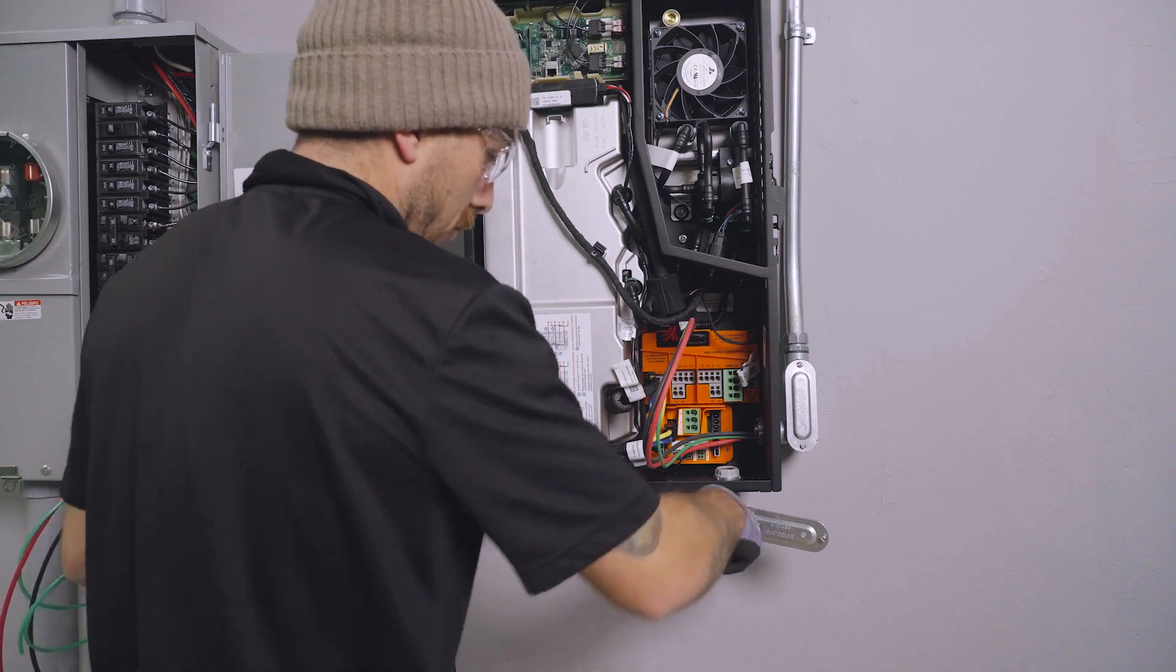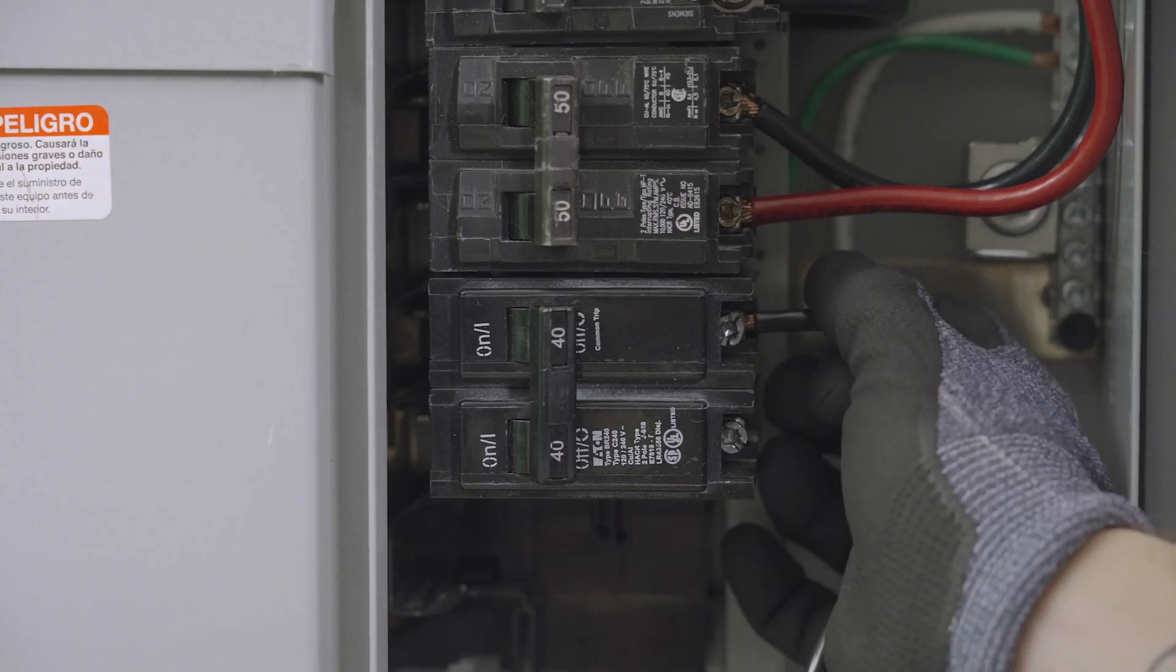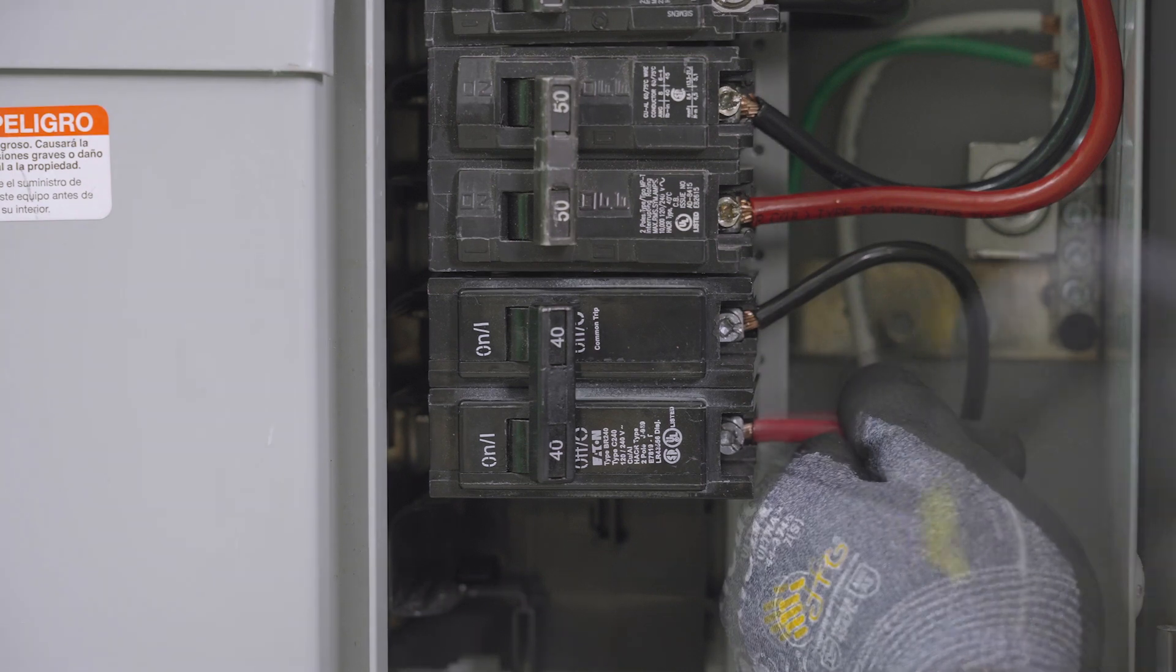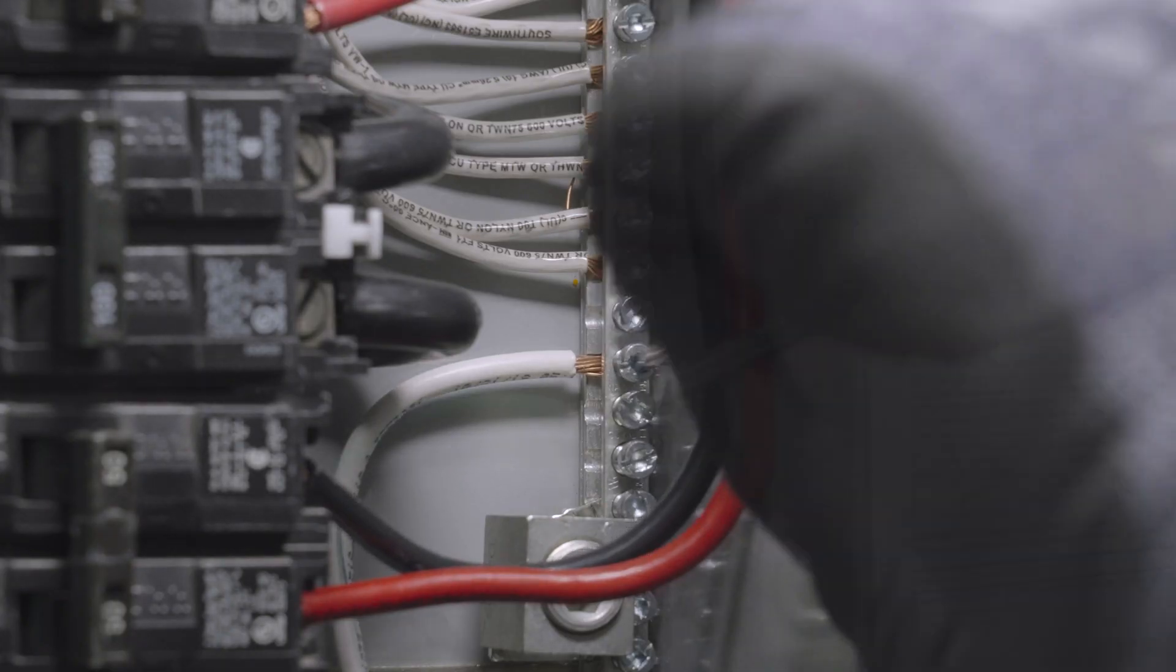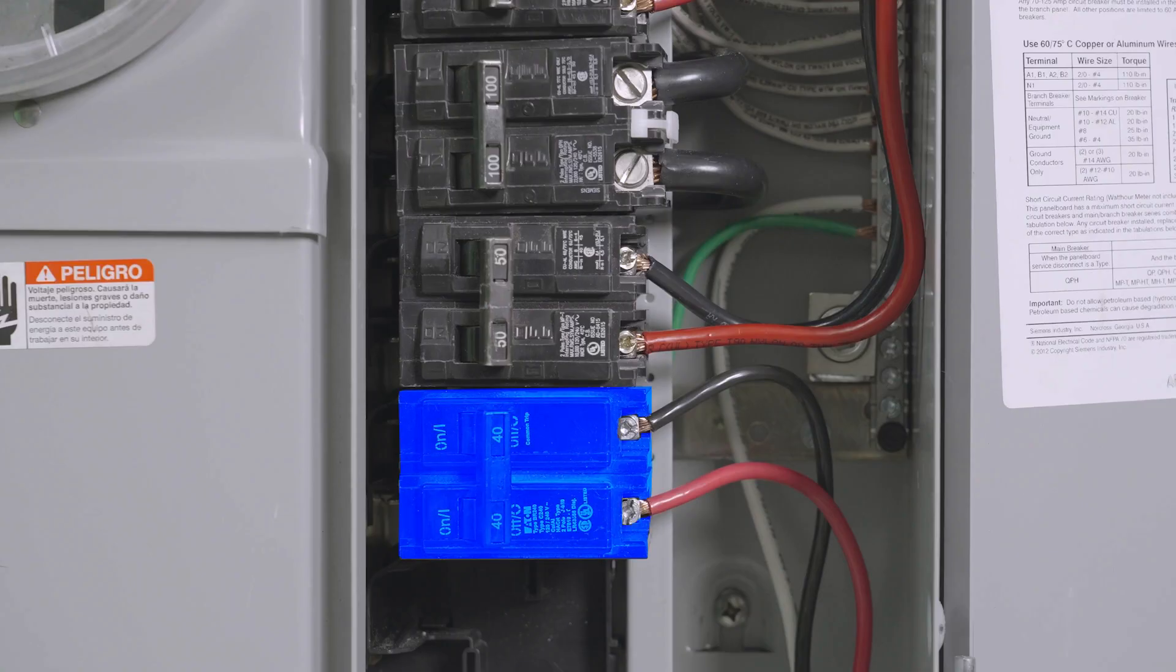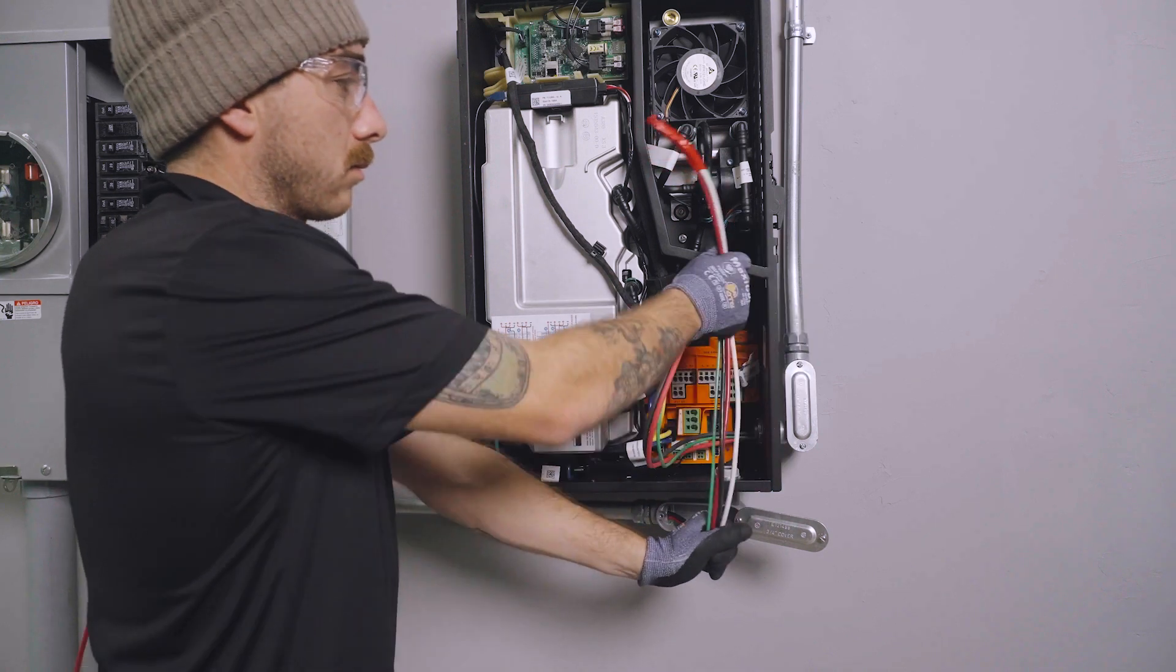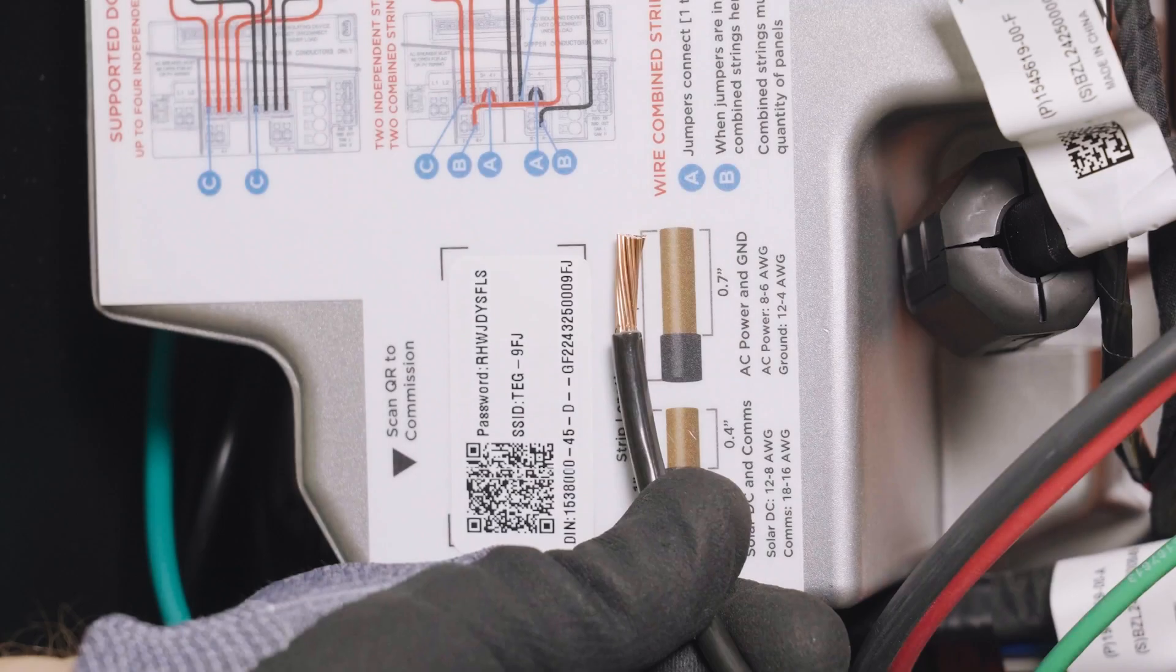Moving on to AC wiring, Tesla's solar inverter includes two line conductors, one neutral conductor, and an equipment grounding conductor. Terminate the two line conductors on an appropriately sized breaker within the home's electrical system. Terminate neutral and ground on the respective bars. Ensure that this breaker is in the off position and is secured against reconnection during the remainder of the wiring procedure. Bring enough wiring into the inverter to comfortably reach these terminals with a service loop. Strip the conductor insulation, as shown here, to prepare it for termination.